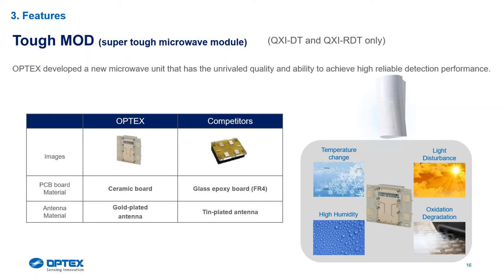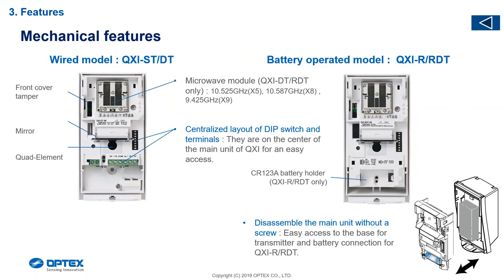On the microwave side, we've changed the design with what we call Tough MOD — we've put a ceramic board on the microwave with gold-plated antennas. Gold plates don't rust, and the ceramic board is a much tougher material. Our competitors use a glass epoxy board with tin-plated antennas. If you open an old microwave detector that's been in the field for two or three years, you'll see it's discolored and the tin starts flaking. With our ceramic board and gold plates, whether you buy the detector a month old or four years old, the microwave is still working 100% to spec.